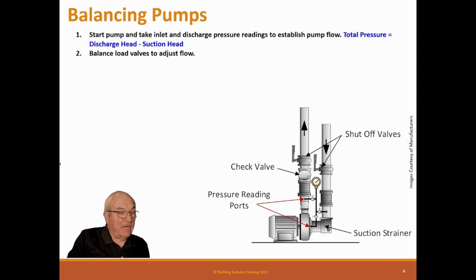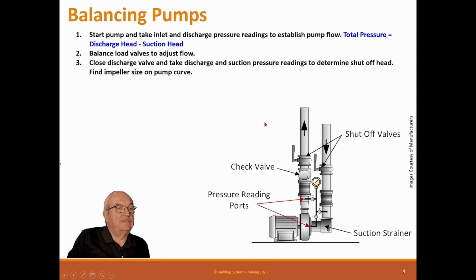Now if everything's a little high, then you come back and change the pump. Now how do you do that? Well, if you're going to balance it and you have no way to do it and you're 3 or 4% over, don't worry about it. Just leave it there. You can run high. High is not a sin, right? Really high is, because it's using horsepower, but if you're 10% high, 12% high, that's not a problem. If you're 40% high, okay, now you've got to make a change.